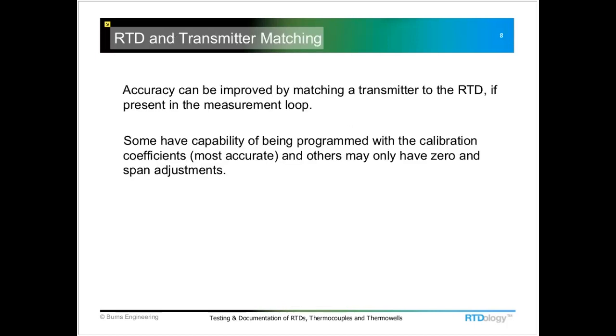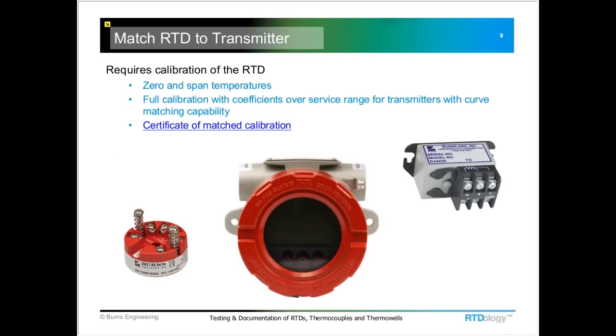One of the ways that we can eliminate that tolerance band, or most of it anyway, would be to calibrate the RTD and match it to a transmitter or some other readout device. And this will generate a document that would define what was done. If we look at matching this specifically to a transmitter, we'll calibrate the probe. So we compare the temperature probe to a known standard. We generate the resistance versus temperature table and the calibration coefficients.